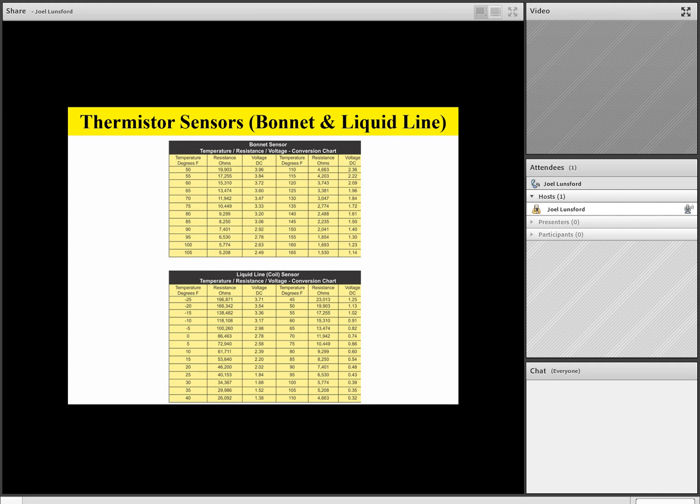But now hang on a second. If you plug that sensor back onto the board at 80 degrees and you sneak your needlepoint meter leads into the harness behind that sensor, you'll notice that it reads 0.60 volts DC with it plugged back on. So all the charts work in a similar fashion. You look at the temperature, you read the resistance with it off the board, you plug it back onto the board, and then you can read voltage.